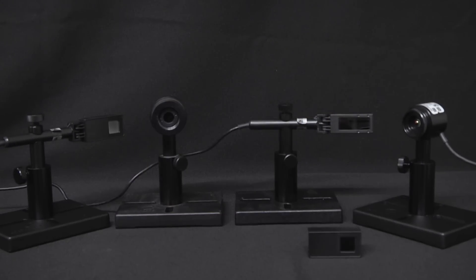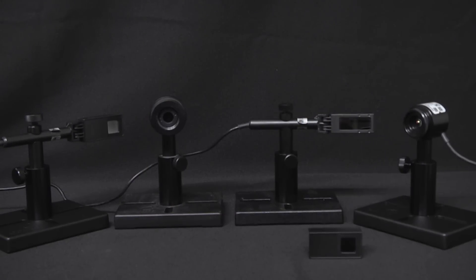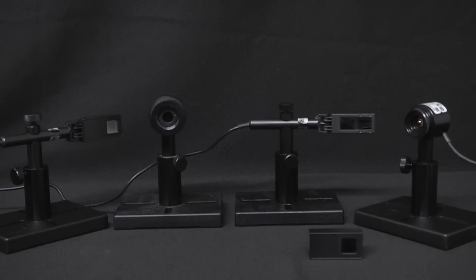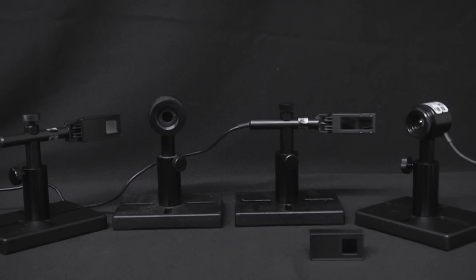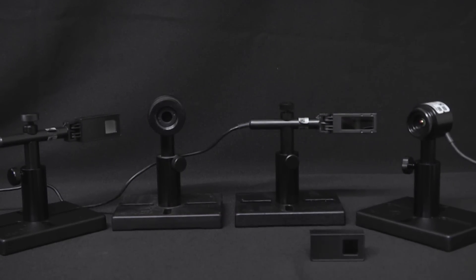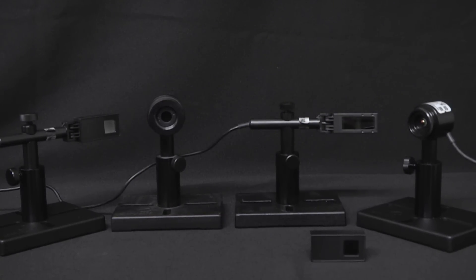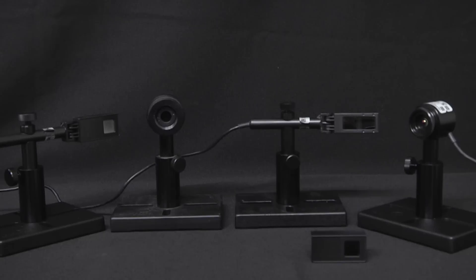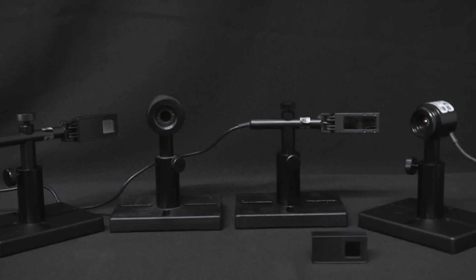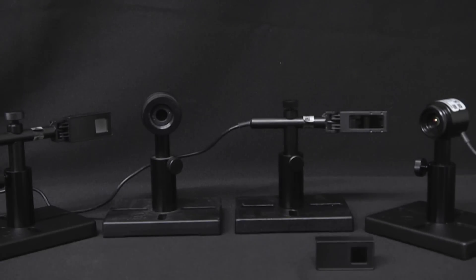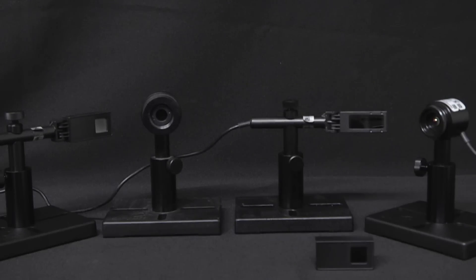There are three main types of photodiode sensors. Silicon for the visible and near infrared spectral range, powers up to 300 milliwatts. There are also models for powers up to one watt and three watts.